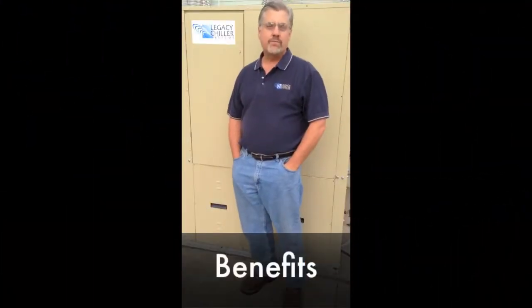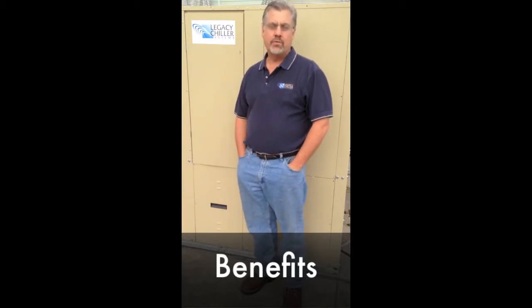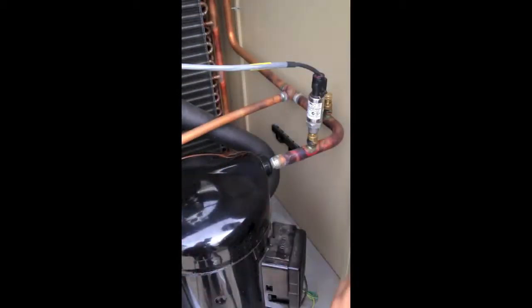Hi, in this video that's part of our process chiller buyer's guide, we're going to be covering the hot gas bypass system. In all of our scroll model chillers, this system is a standard feature, and it's a very critical system in preventing damage to the chiller's evaporator under low load and low ambient conditions. I'm also going to show you on screen, as well as in this chiller here, how this system operates.